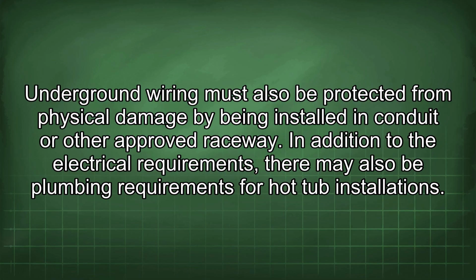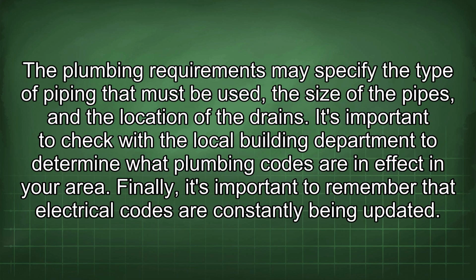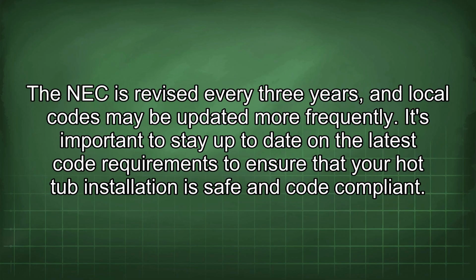In addition to the electrical requirements, there may also be plumbing requirements for hot tub installations. The plumbing requirements may specify the type of piping that must be used, the size of the pipes, and the location of the drains. It's important to check with the local building department to determine what plumbing codes are in effect in your area. Finally, it's important to remember that electrical codes are constantly being updated. The NEC is revised every 3 years, and local codes may be updated more frequently.